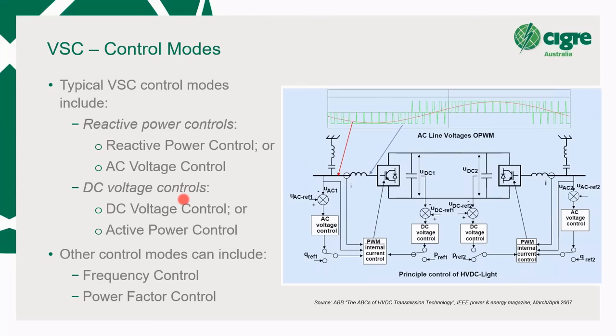Now, on the DC side, as I mentioned about making the power flow across the line, you have a DC voltage control and you have an active power control. One converter must be DC voltage control, one must be active power control. If you go into multi-terminal VSCs, it gets a little bit more complicated, but using the point-to-point, it's quite easy to understand. So you control the voltage at the set point at one end, and the other end, which is the end that the operator is typing in an active power set point, is adjusting the DC voltage.